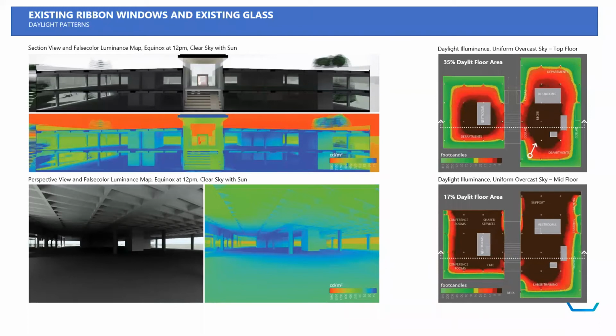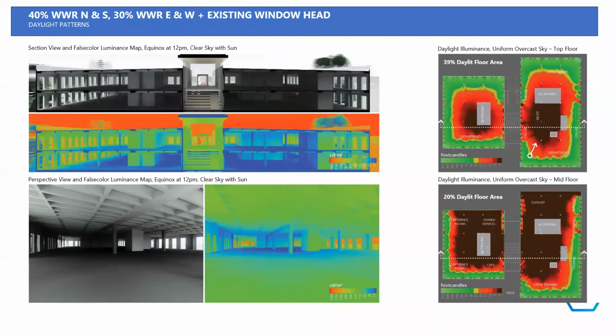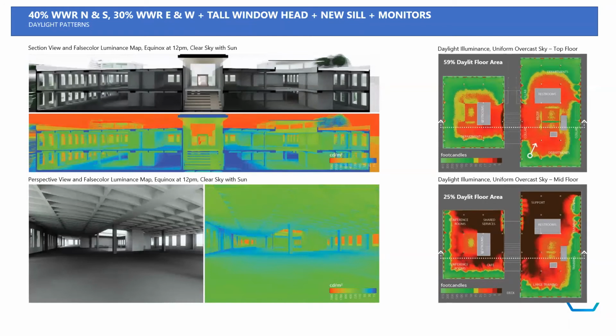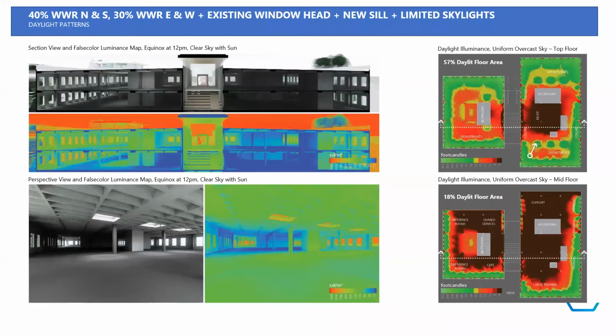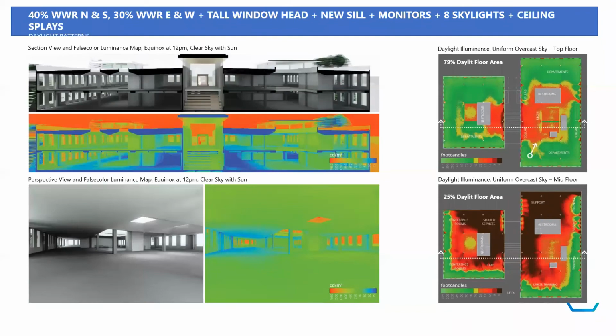So existing ribbon windows give you quite a bit of daylight, almost excessive daylight. 40% window relationship on the north and south, 30% on east and west, with existing headers and existing window size with the 40% reduction in the windows. There's a pretty good daylight area. We also looked at taller windows, new sills and monitors, limited skylights. And actually, this is really where we ended up, existing window heights and the limited skylights, which are 18. And we feel that it gave us very good daylighting at the top floor and reasonably good daylighting on the smaller area of the building on the mid floor. And the largest area of the building, again, was the training center. That gives you an idea of all the analysis we did.